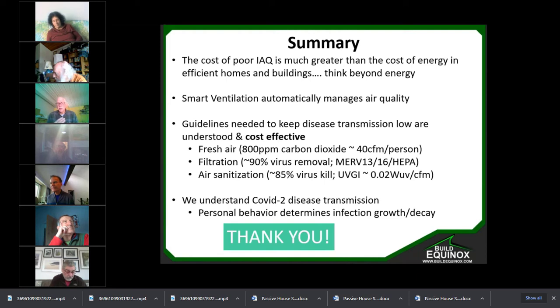And then by sensing directly the CO2 and VOC levels, and as particulate sensors get to a level that we can trust. Currently all particulate sensors, yeah, they're interesting, but it's a $10,000 instrument to do that properly and to keep calibrated. And today's particulate sensors that you're seeing in home monitoring, they're maybe good for the 90-day or 1 year warranty period, but certainly they're not at a level that you're going to put in something that's got a 5-year warranty or more. But that's why you gain a lot of energy efficiency.